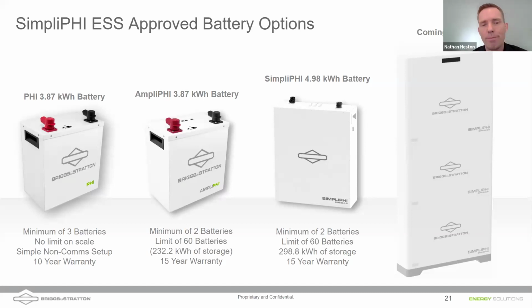Communications give the battery an ability to do things like control its output rate or recommend output rates to the inverter based on internal temperature. They give the inverter the ability to surge, knowing that your battery is kept safe. With a non-communicating battery, the inverter is moving ahead with preset settings that may or may not be appropriate for the conditions that the inverter is currently in.